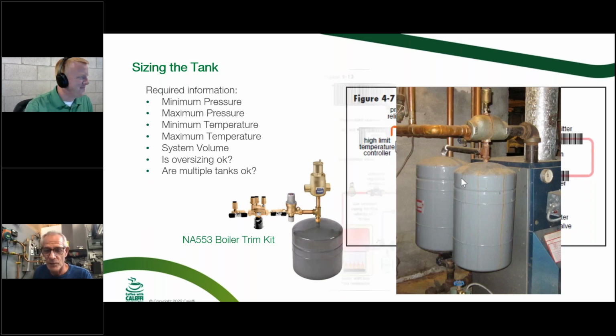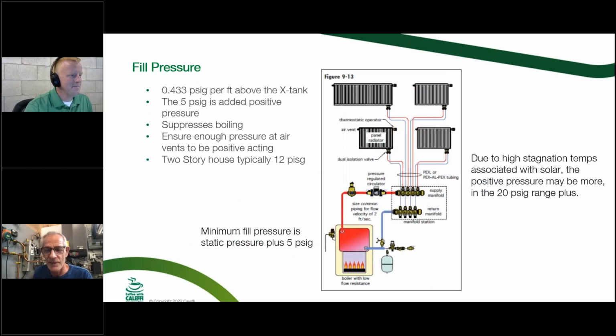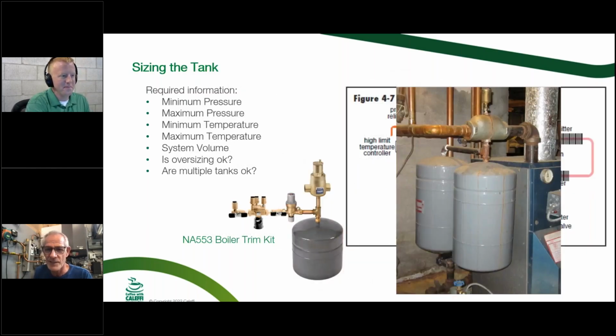Also, what I would point out is that the air separator in there probably isn't doing much work, because you really want to have about 18 inches of straight pipe in front of that so that the water can slow down. I had one of the contractors at one of my seminars tell me, well, that's just a coupling, that's not an air separator. It's a really heavy coupling. Yeah, maybe it's a cross fitting instead of a coupling, but that was a good point. They're not doing what you think they're doing.